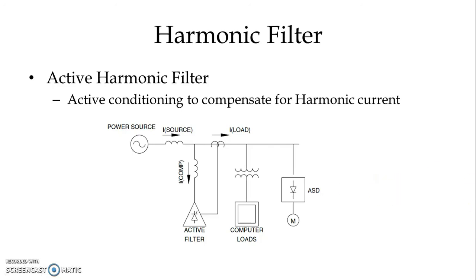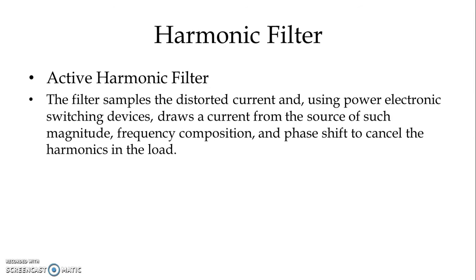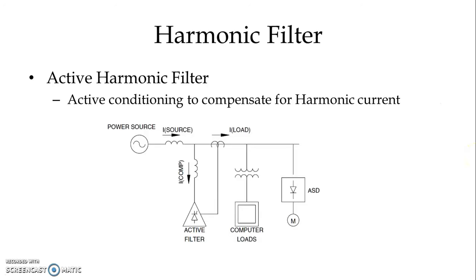We use an active device for eliminating certain harmonics. The filter samples the distorted current and, using a power electronic switching device, draws a current from the source of such magnitude, frequency composition, and phase shift as to cancel the harmonics in the load. We sense the distorted current, and as per the sample taken, the active filter responds accordingly.